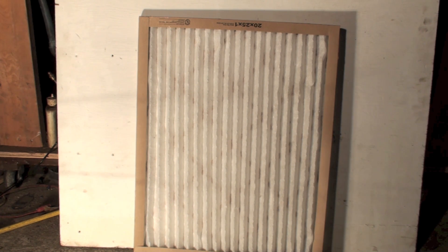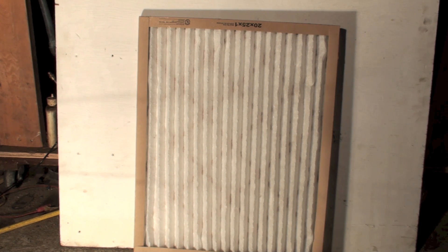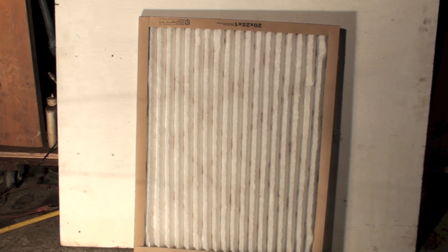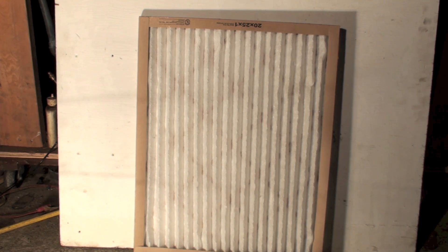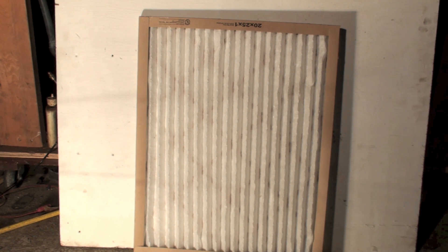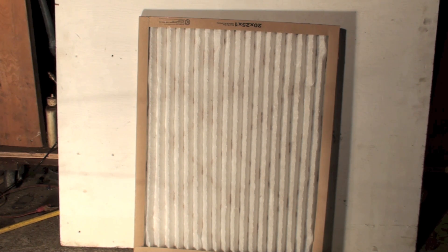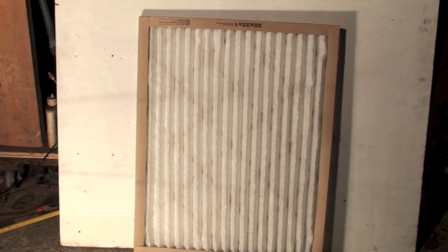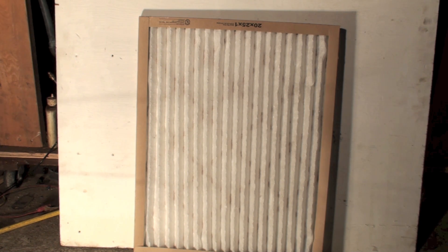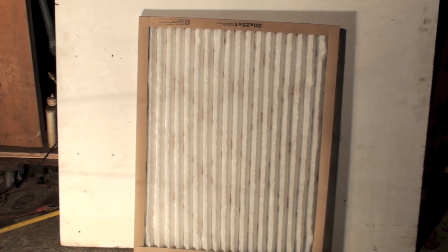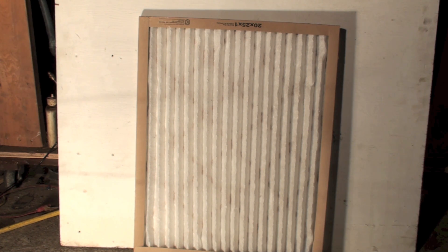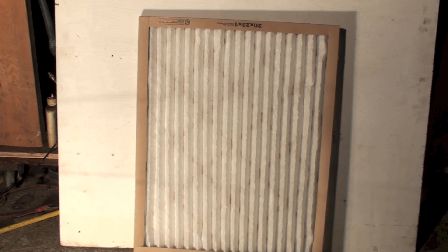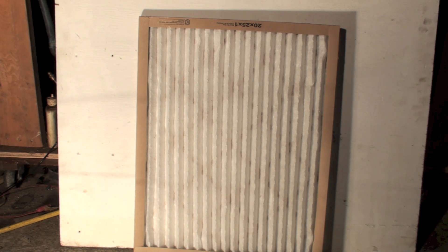They're fairly common. This one's probably, I don't have the numbers on this, probably 30 to 35% efficient. It's okay. One of the problems with these pleated type filters, if you get more efficient ones, you tend to have quite a bit of pressure drop across your furnace. So you don't want a lot of pressure drop because that's going to reduce efficiencies and so on.